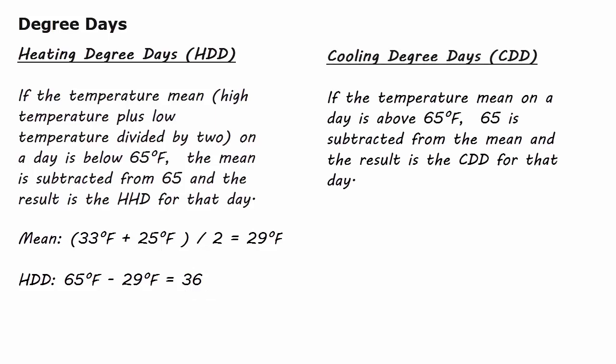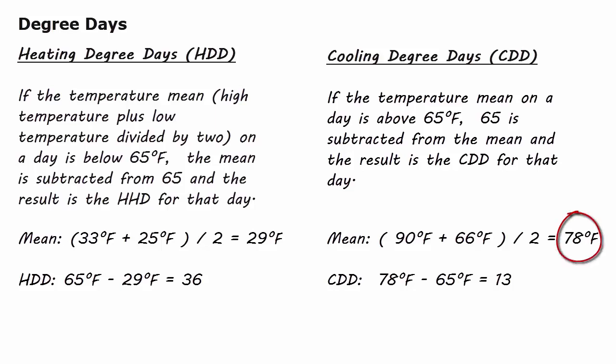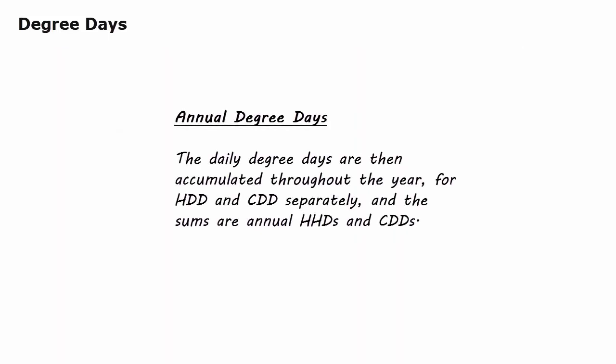For cooling degree days, if the temperature mean on a day is above 65 degrees F, 65 is subtracted from the mean. For example, if the high is 90 degrees F and the low is 66 degrees F, the mean is 78 degrees F. Because the result is above 65, this counts as a cooling degree day: 78 minus 65 equals 13 cooling degree days for that day. The daily degree days are accumulated throughout the year separately for heating and cooling to produce annual heating degree days and cooling degree days.